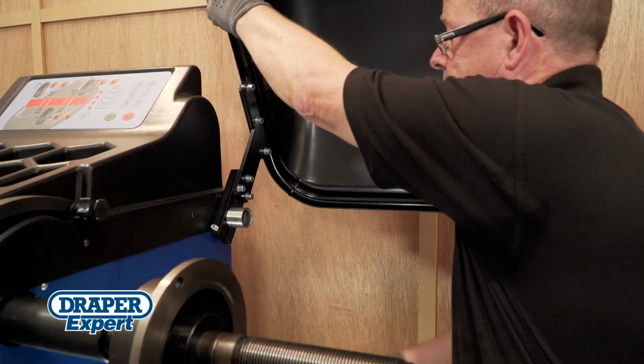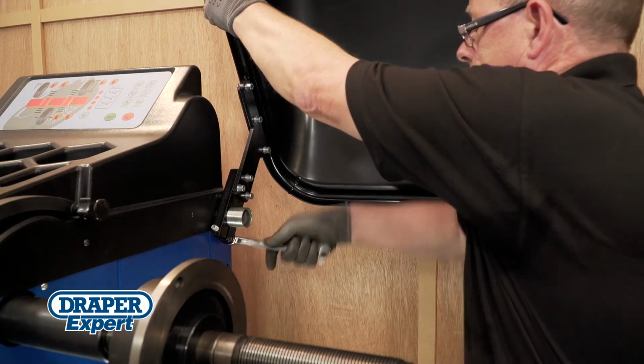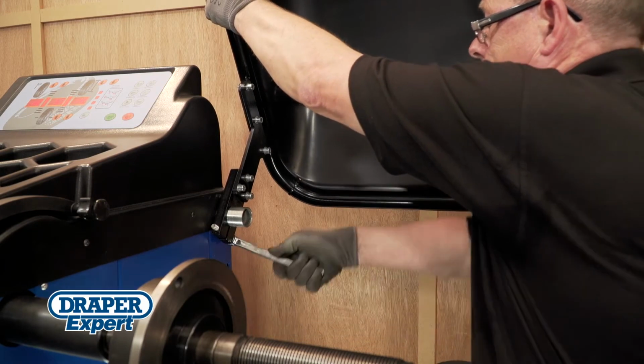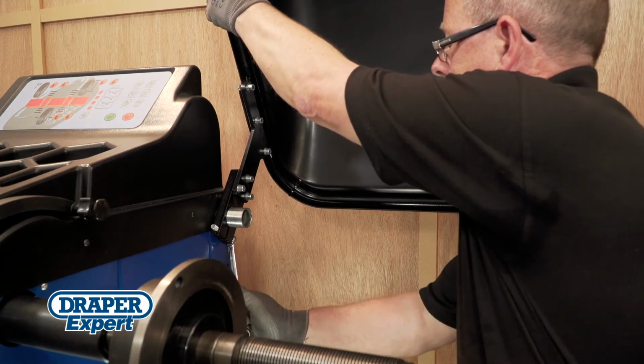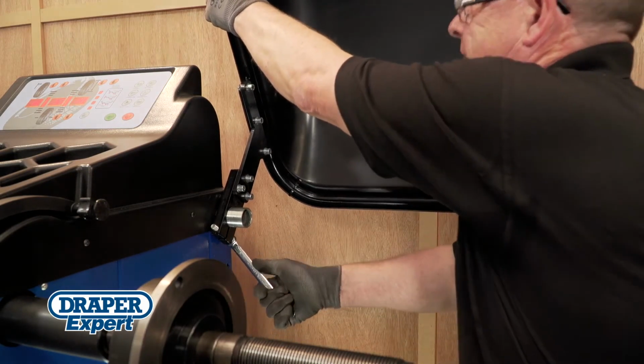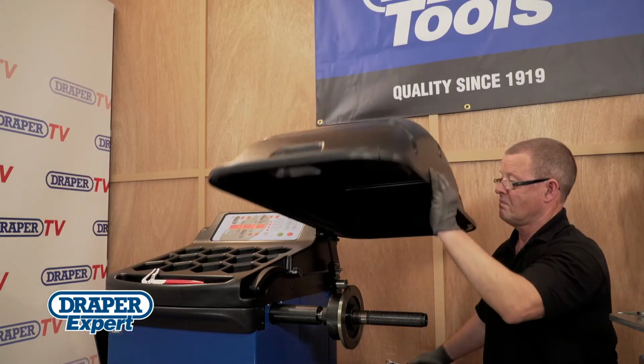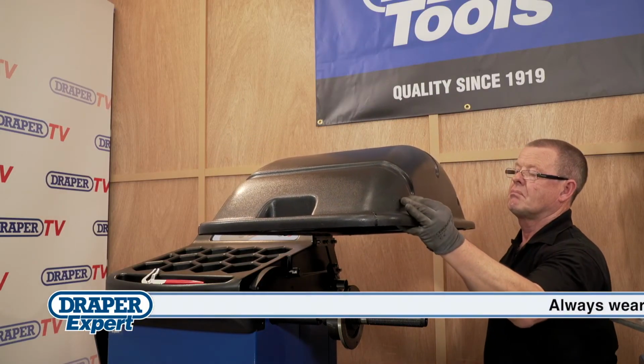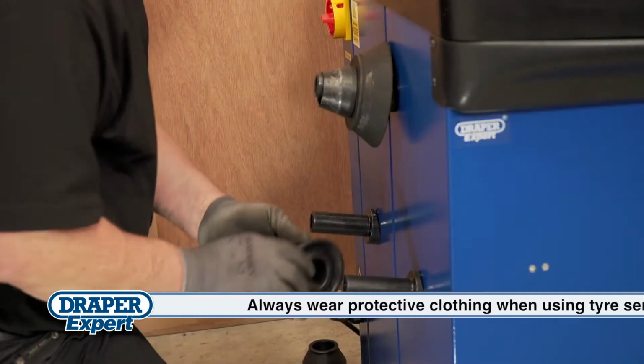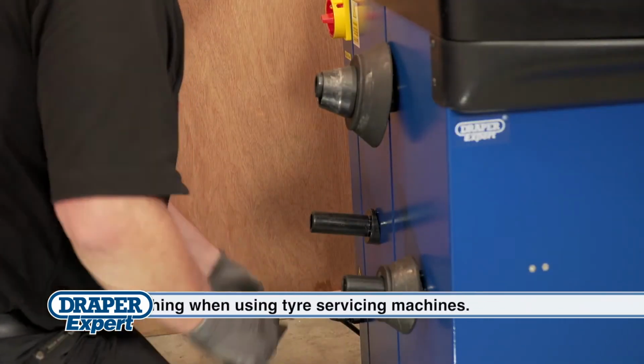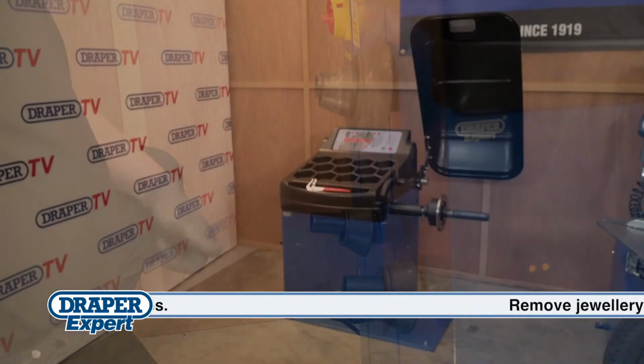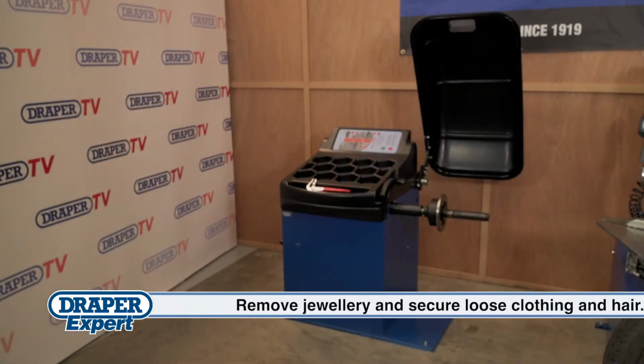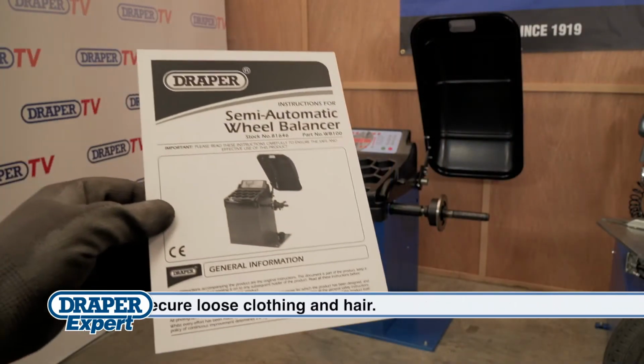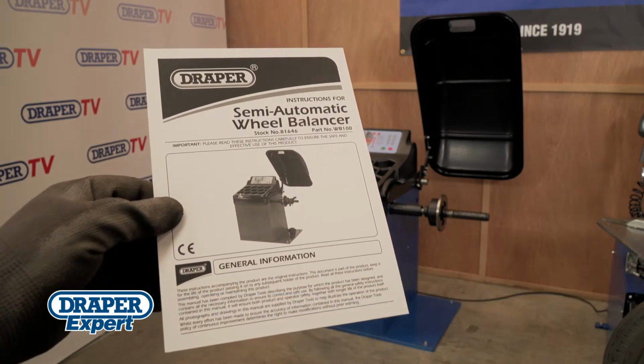The first step is to attach the wheel safety guard to the balancer by sliding the guard onto the shaft, and secure it in place by tightening the clamp bolts, ensuring the safety guard is level when it's in the lowered position. Finally, attach and secure the cone holders to the side of the machine. Once the machine's been installed and set up, it needs to be calibrated. It's all explained in this manual, but let me show you how easy it is to do.